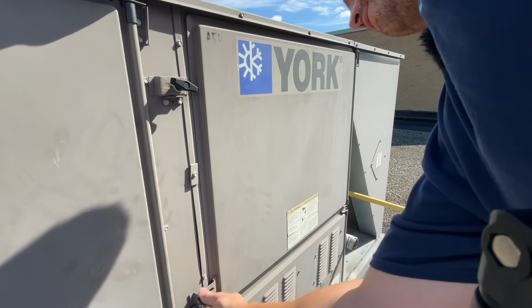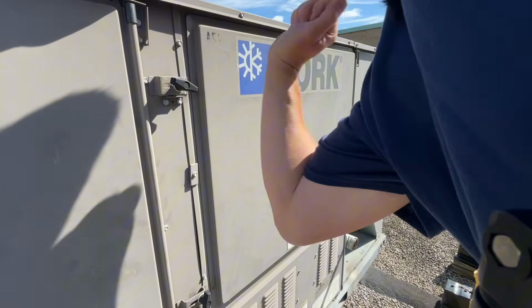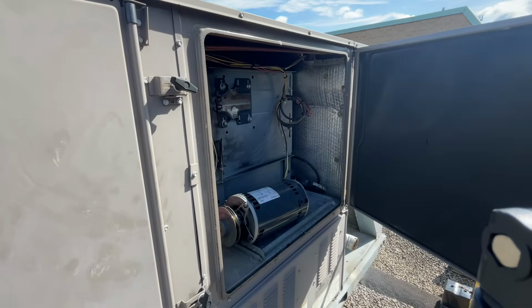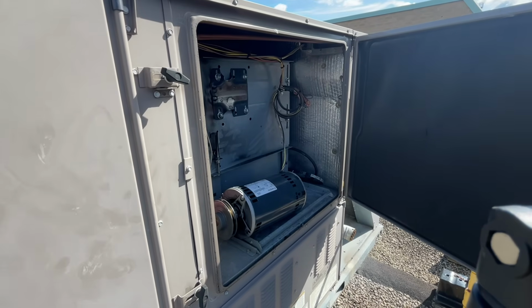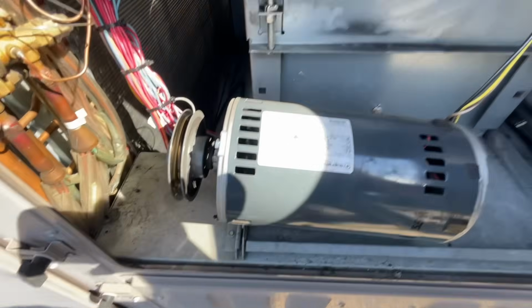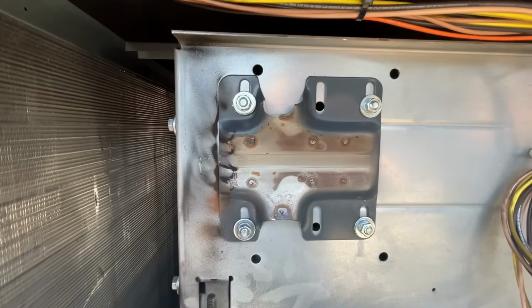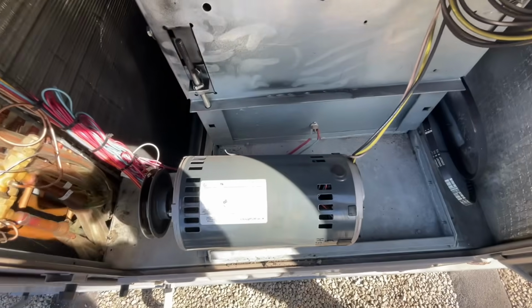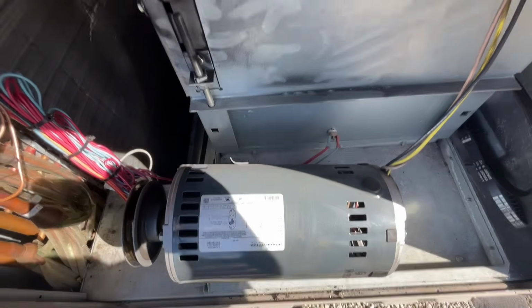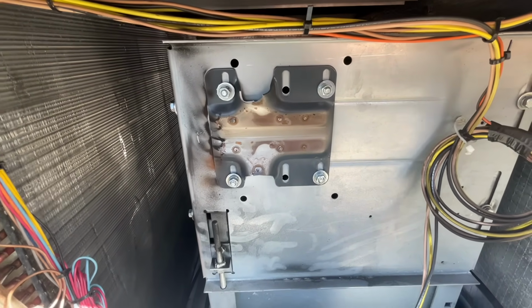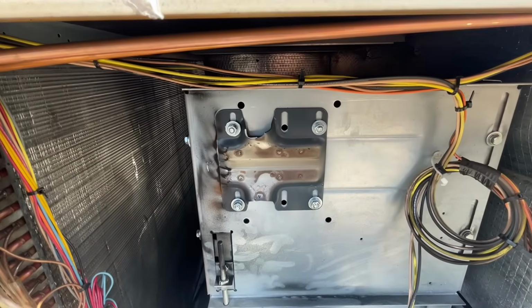We got an A54 in here. It's written here with marker. Oh my God. What the hell is this? This blower motor here, at one point in time, sat on that bracket. I honestly can't say I've ever seen a blower break off that steel mounting before. That is insane. Let's shut this power off and investigate a little bit here.